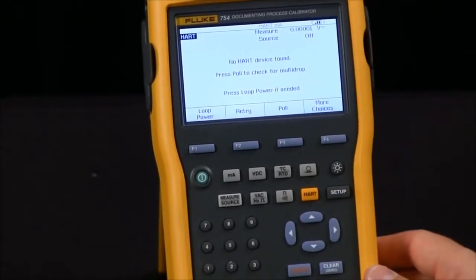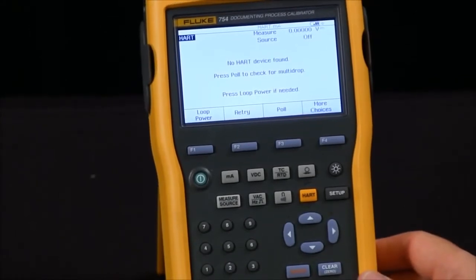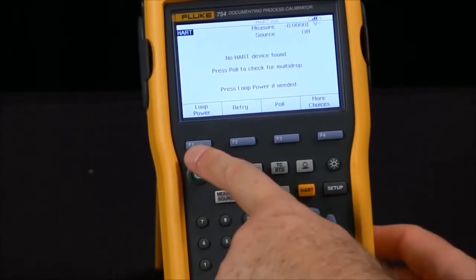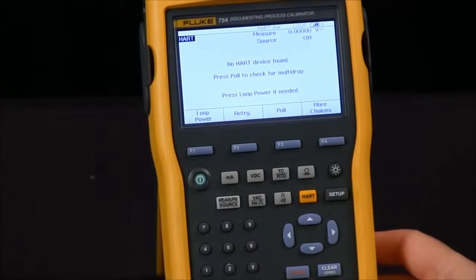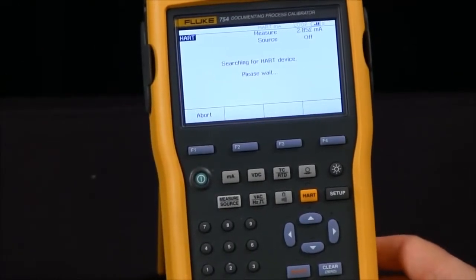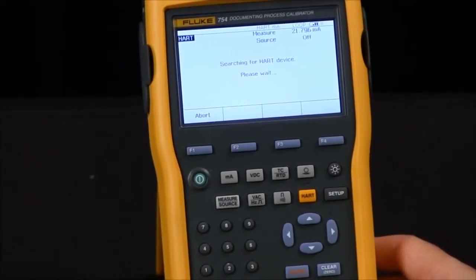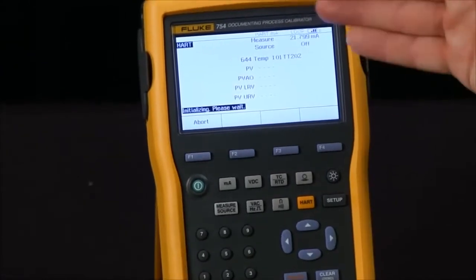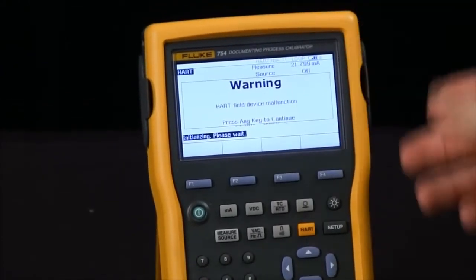You see I'm expecting an error message because it went out there. It says searching for HART device and none found, but it does give me an option on the F1 key to turn on loop power. I will do that, and then once again it will go out and look for the HART device, and we'll see that it has found. It will give me all of the parameters of the device.